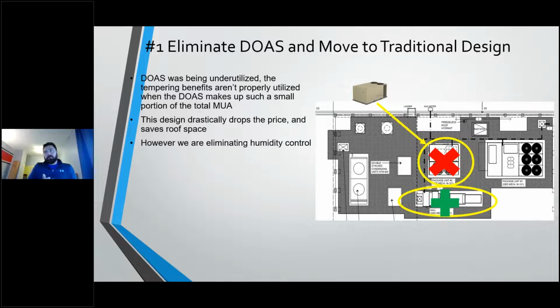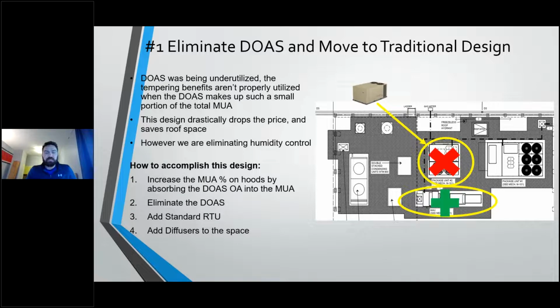So in that first example, that DOAS system was being underutilized for the tempering benefit since it was such a small percentage of the overall makeup air. So this design is going to drastically drop the price of the project, and it's going to save on roof space. So what I'm going to do is increase the makeup air in my hoods by absorbing the DOAS's outside air. I'm going to add a standard RTU, and then I'm going to add diffusers for that RTU unit, and I'm going to bring my makeup air for my dedicated makeup air fan in through one of those ASP plenums that's going to almost immediately exhaust most of the air, but at least when that air gets in there, it's going to be tempered to that heating and cooling, but it's not going to be as expensive as that first option.